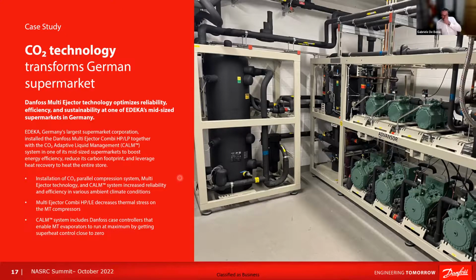And with the installation of a CO2 system in the supermarket, they were able to boost efficiency and have a consistent reduction of the carbon footprint of each single store. And also thanks to the application of a heat recovery solution, to provide heating to the store, heating given by the excess heat that the refrigeration system is providing.